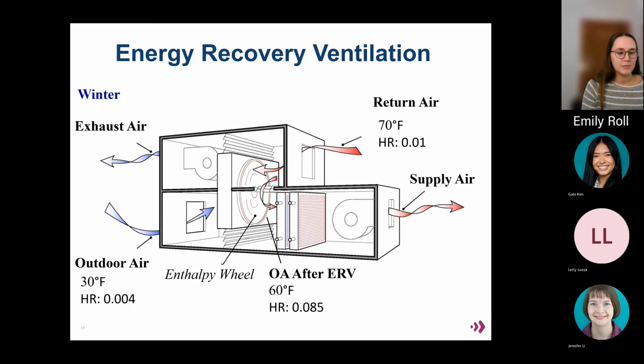Now, at the same time, the system is also exhausting already conditioned air that will be replaced by the fresh outdoor air. This exhausted air, when it first enters the makeup air unit, is called return air. As you can see in this diagram, the return air is coming to the makeup air unit at 70 degrees, and the outdoor air is at 30 degrees. Instead of just exhausting the return air, we first put it through an ERV, in this case, an enthalpy wheel. The enthalpy wheel then transfers the heat from the return air to the outdoor air. You can see here the outdoor air after the ERV gets to 60 degrees.